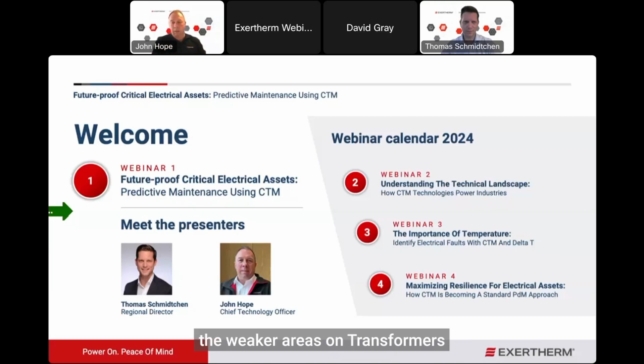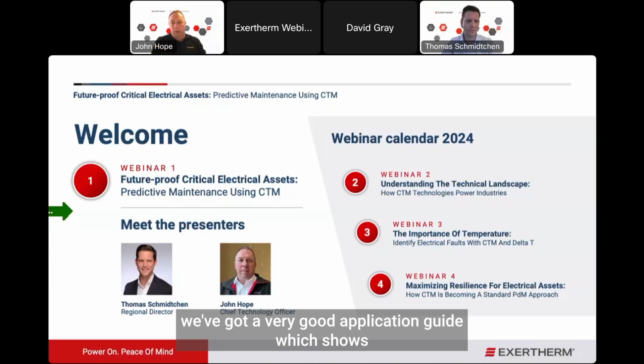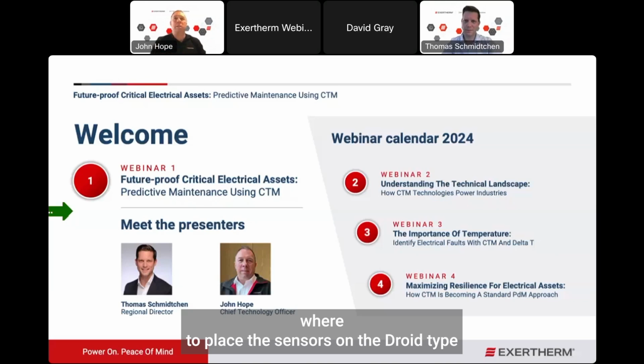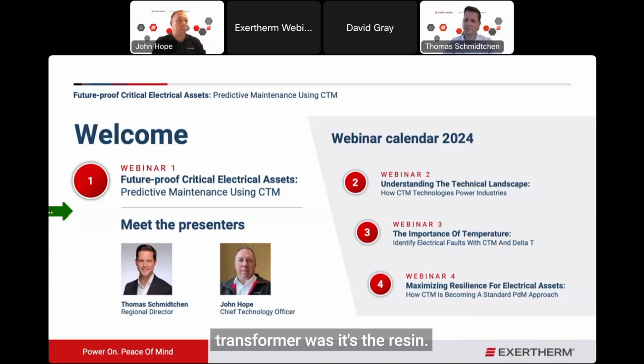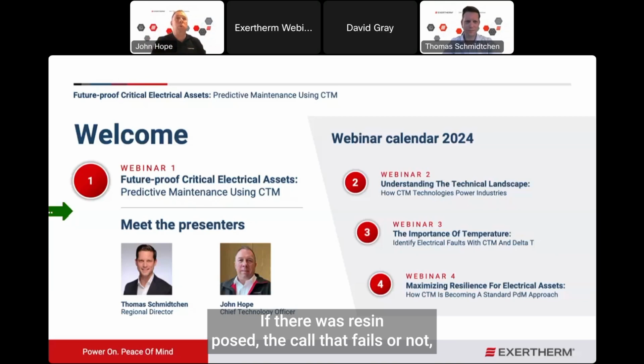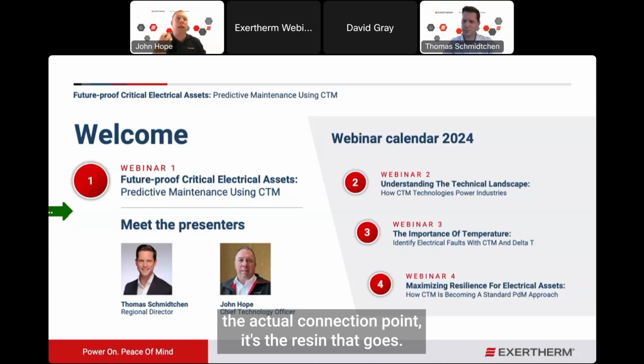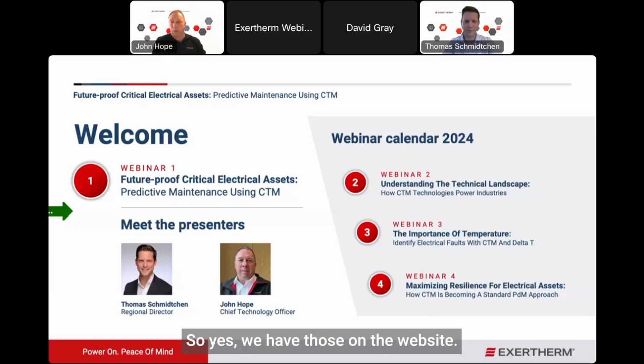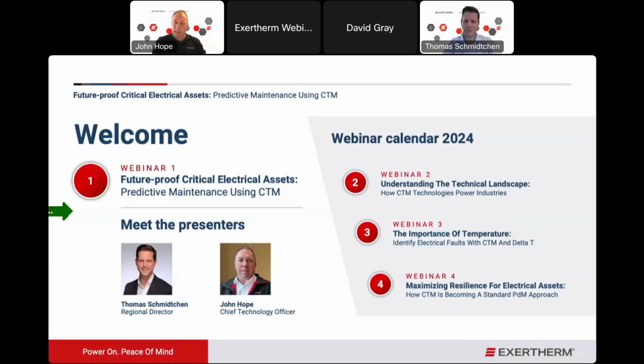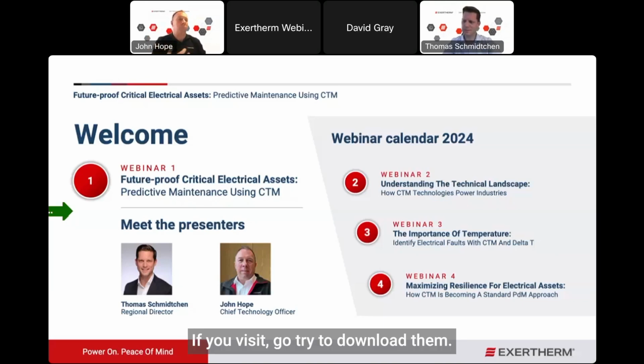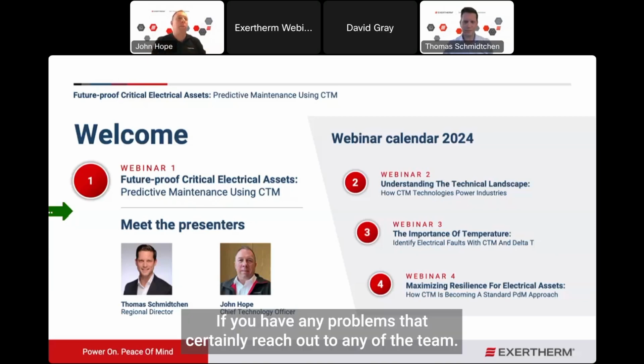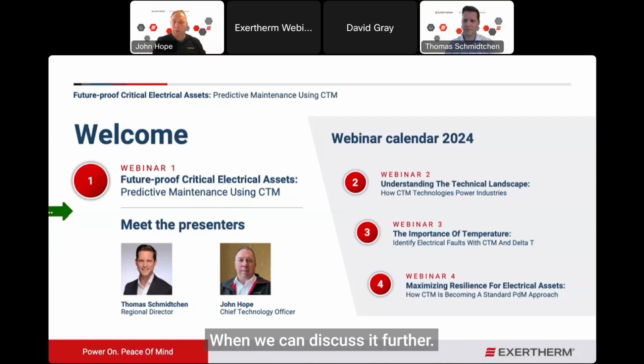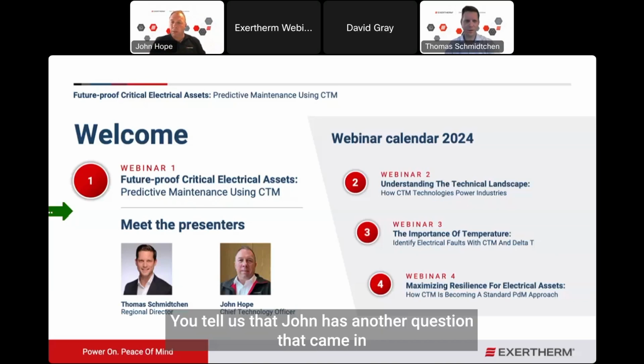They're the weaker areas. On transformers, we've got a very good application guide which shows where to place the sensors on the dry type transformer. Whereas it's the resin, those resin posts, the core that fails, not the actual connection point. It's the resin that goes. So yes, we have those on the website. If you try to download them and have any problems, then certainly reach out to any of the team and we can discuss it further. Anything else you found there, Thomas?